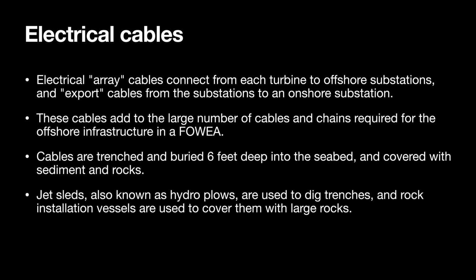Array cables may or may not be trenched, but the HVDC export cable usually is. They are buried 6 feet into the seabed and covered with sediment and rocks. This is done using a cabling vessel and a jet sled, also known as a hydroplow, which digs a trench and lays the cable. Rock installation vessels are then used to cover the cables.